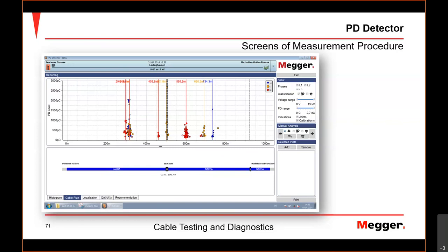If the cable is not so important and we don't have the time, we don't have the money, we don't want to do it, we keep it in mind that it's there and we leave it running. Or you say, well, we cannot leave it running. We have to provide a certain reliability of the network, and it's an important cable going to the airport. So we better fix it quickly. And you might even say that when you see something below 1,000, hey, there's a concentration. Let's do something about it.